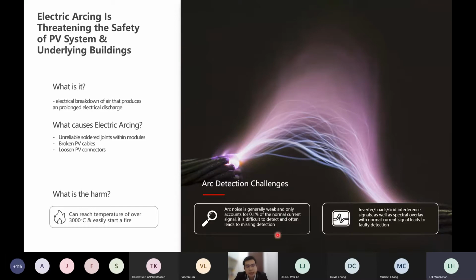And to detect this arc fault is quite a challenge. As mentioned here, the arc noise is generally very weak and it only accounts for 0.1% of the operating current. So it's very difficult to detect this arc fault. Another challenge would be the interference, for example from the inverter. The inverter is packed with power electronics, so during its operation, it will cause interference. And then the load, and also you have the grid interference as well. So to detect this arc fault signal is pretty tough.